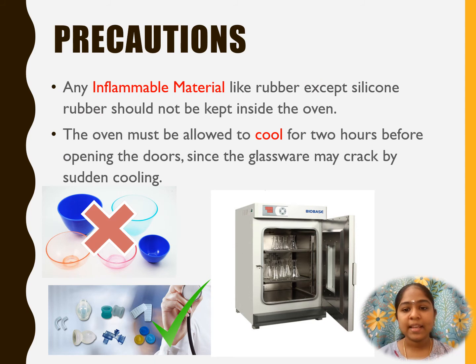Rubber materials except silicone rubber will not withstand the temperature. Hence, they should not be kept inside the oven. The oven must be allowed to cool for 2 hours before opening the doors, since the glassware may crack by sudden cooling.